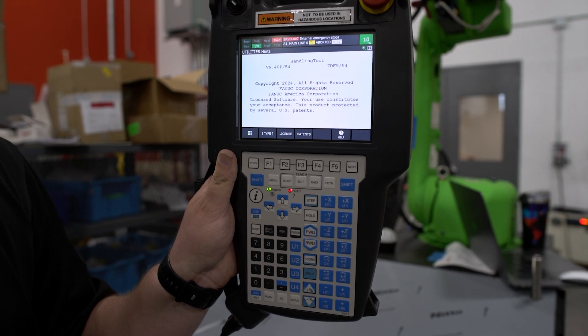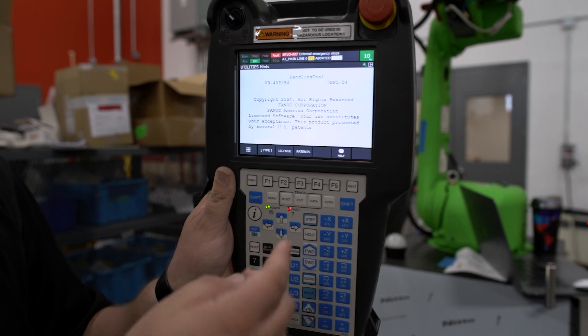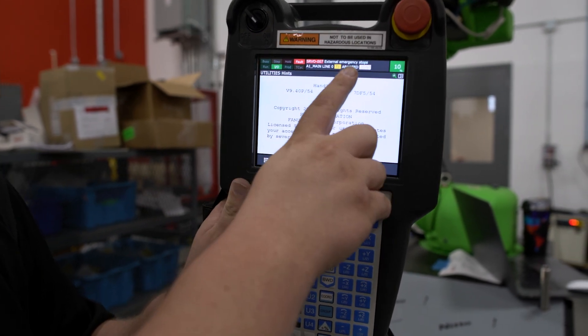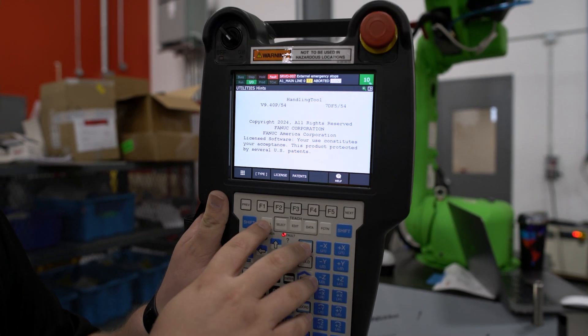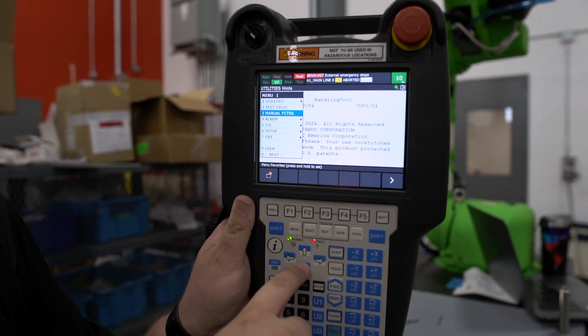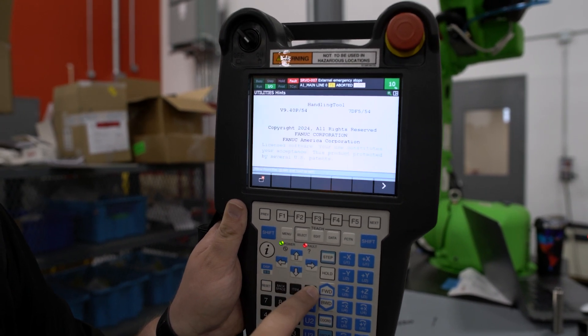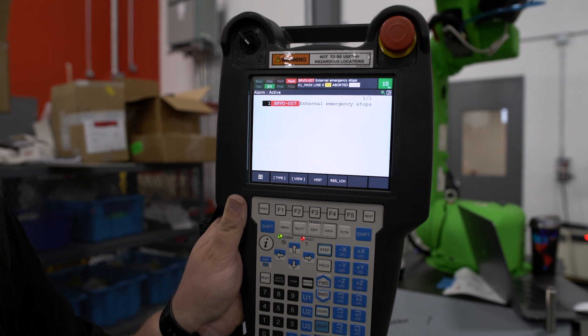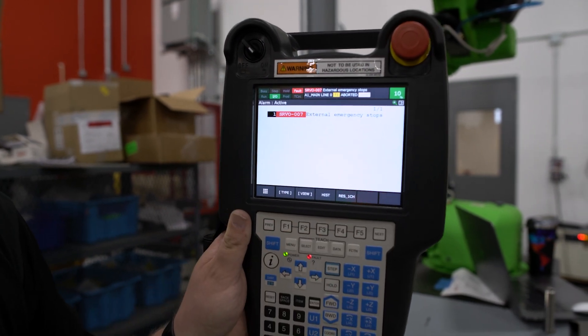In order to get more information, we will come to our teach pendant where it does indicate that we have an external emergency stop. To see more information, we will go to our menu button, cursor down to 4 for alarms, and look at our active alarm screen where we can clearly see that we have an external emergency stop.